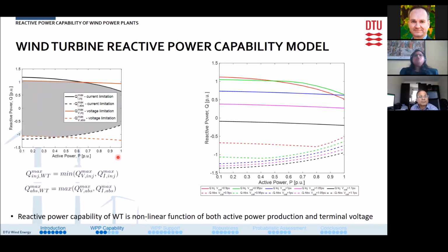If we draw the active power and voltage dependent reactive power capability, we get something like this, where each of these colors represents a specific voltage level. We can see that this red one is for low voltage, 0.9 pu. Correlating with this graph, we can see that at low voltages, the reactive power capability is mainly converter current limited. Whereas for high voltages, as for example in this pink curve, the capability is mainly converter voltage dependent. And also we can see that the capability curves are non-linear in nature.